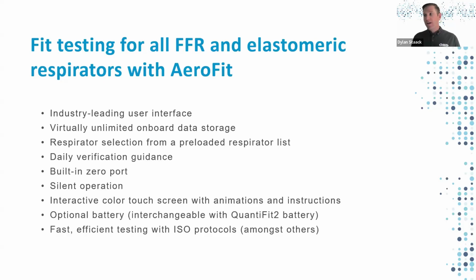The next one is the one that I think I personally take a lot of pride in because I helped design this. It's the daily verification guidance. So daily verification on a CNC fit test machine can be tricky, especially if you're doing both filtering face piece or N95s and elastomeric respirators, because there are two different technology methods for counting those particles. You have to validate both of those.